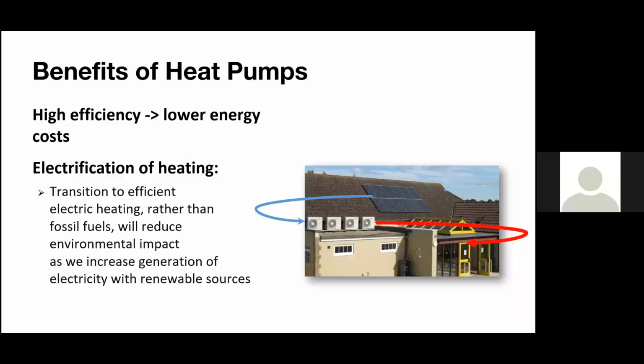In the winter, though, this is where heat pumps introduce electrification. That's the concept of, if we're trying not to burn things to heat our building, not to burn natural gas or use boilers or furnaces, we need to heat the building somehow. Again, we can use electric resistance heating. That's very expensive and very inefficient to do. That tends to be not all that popular. The other way to do this is we extract heat from somewhere, whether we extract it from the air, which is an air source heat pump, or we extract it from the ground or a lake or water, which is where water source heat pumps come into play, which I'll touch on in a few slides.